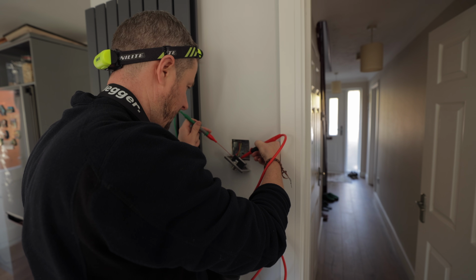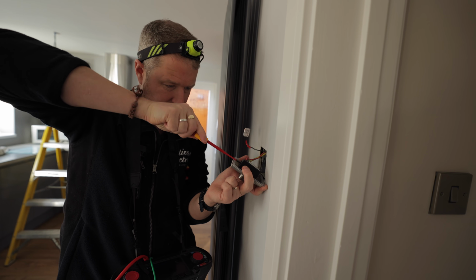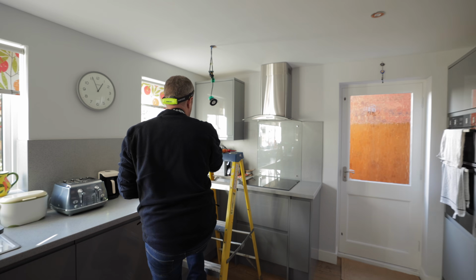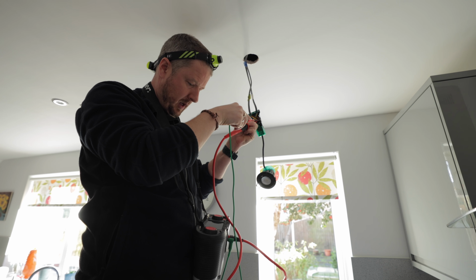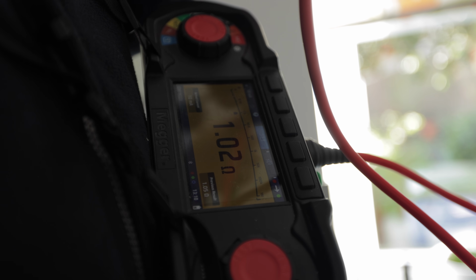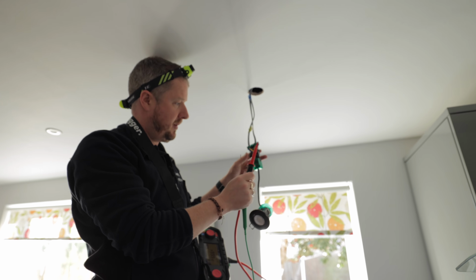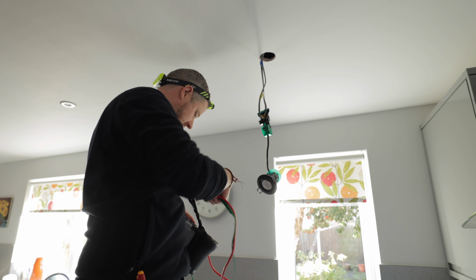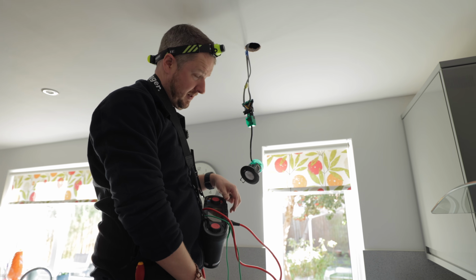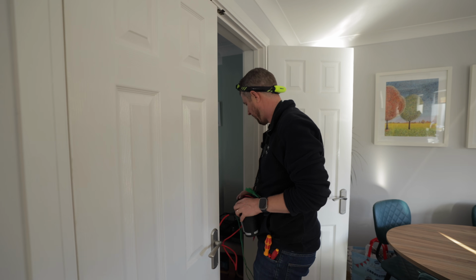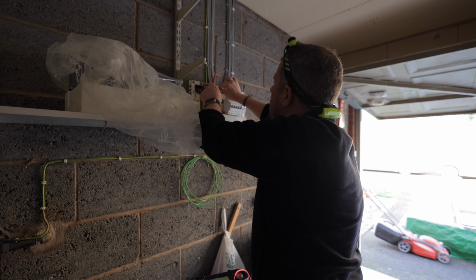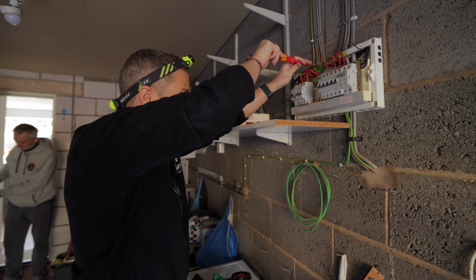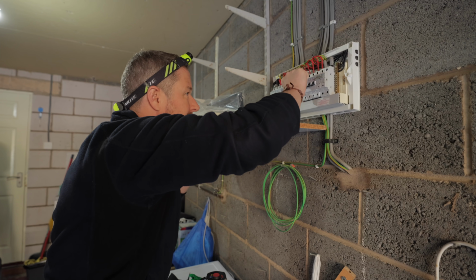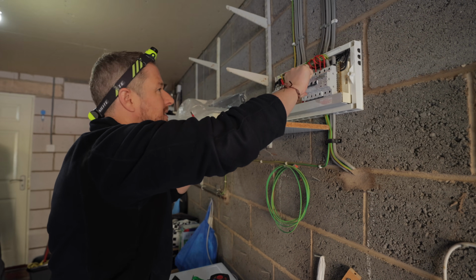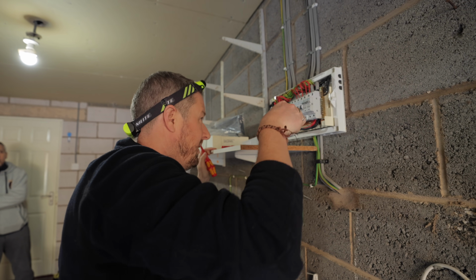So we've got an earth here, so that's good. Polarity's correct here. So now that we've bridged those out, we should have a low resistance at our light fitting. Yeah, much better. So we've got like 1.2 ohms, which means that we do have earth continuity here, and the polarity is correct. So the plot thickens. Okay, you've got a lot of metal lights everywhere, which, yeah, I've got an idea. It might be that we've got a neutral issue. When you turn the light on, it's going to short out properly. I mean, the breaker is a little bit loose. I don't think that's what's causing the problem, but that might be a side point.